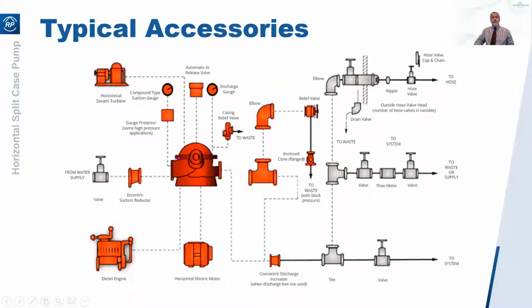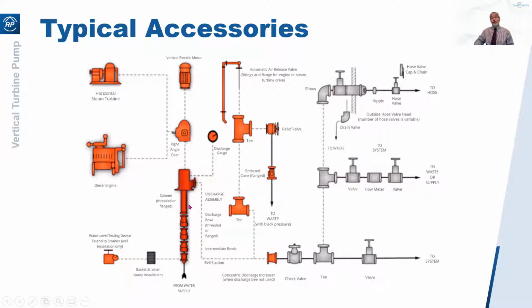So typical design and installation. The pump supplier will often supply all these auxiliaries, accessories that we show here in red. So obviously the motor is required, the diesel engine, possibly steam turbine. Like I say, I never have done so, but it could be done. Casing relief valve, main flow relief valve. These are commonly supplied by the pump supplier. These, shown in grey, are normally we can supply, but the pump suppliers wouldn't normally supply. They would be accepted as part of a packaged equipment package. The user would probably buy and install these. So these are the accessories here for a horizontal pump, and here much the same thing for a vertical pump.